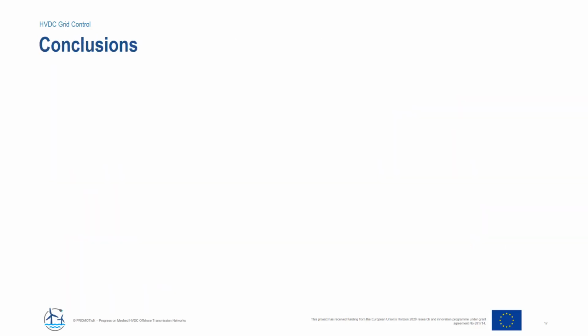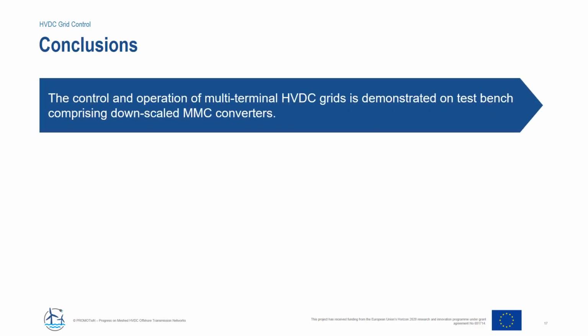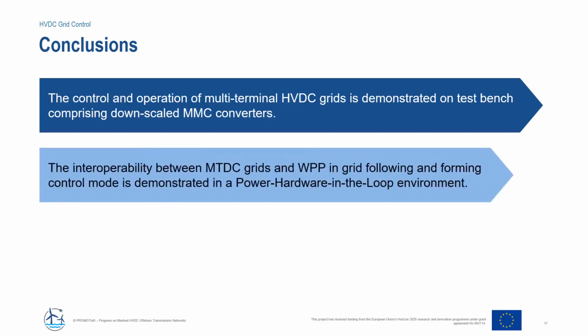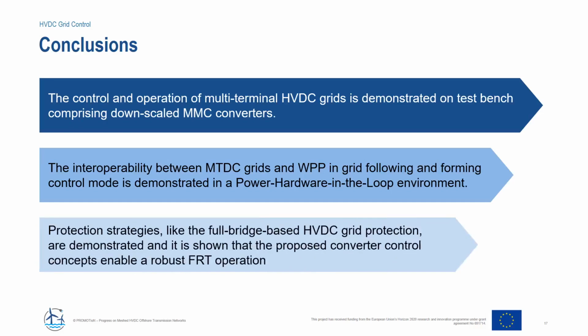With this, I would now like to conclude our results on the HVDC grid demonstration. First of all, the control and operation of multi-terminal HVDC grids is demonstrated on a test bench comprising downscaled MMC converters. Secondly, the interoperability between multi-terminal DC grids and offshore wind power plants, on the one hand in grid following, on the other hand in grid forming mode, is demonstrated in the power hardware in the loop environment. And last but not least, the protection strategies, like for example the full bridge based HVDC grid protection strategy, but also the DC bypass switch concept, are demonstrated, and it is shown that the proposed control methods enable robust fault ride-through operation.